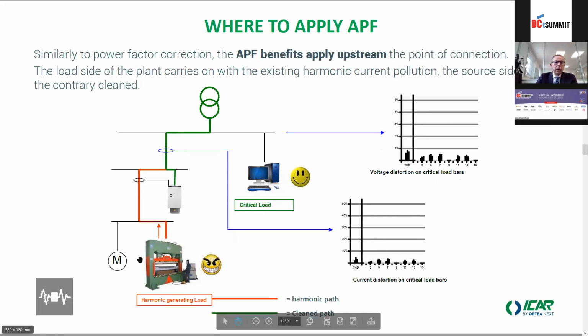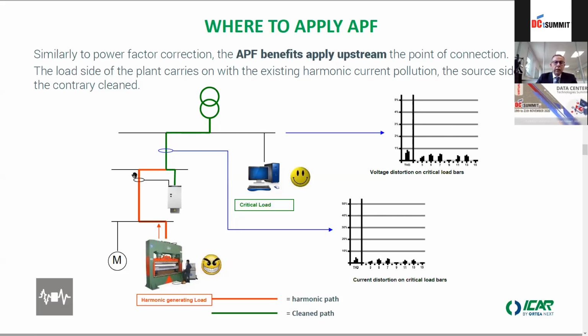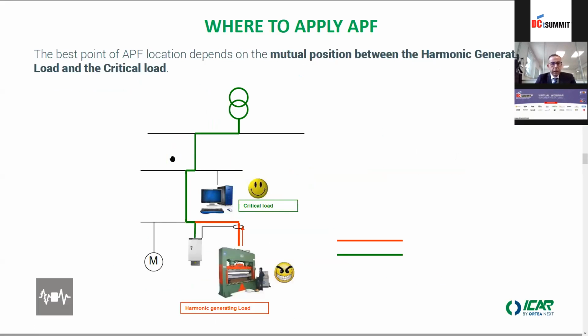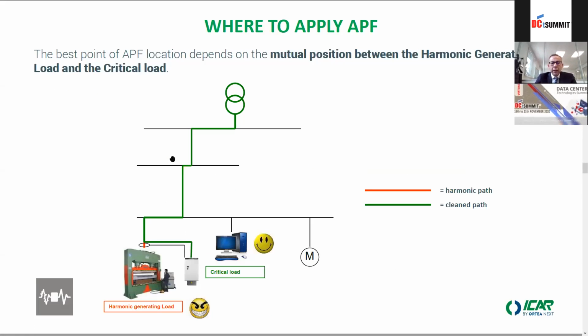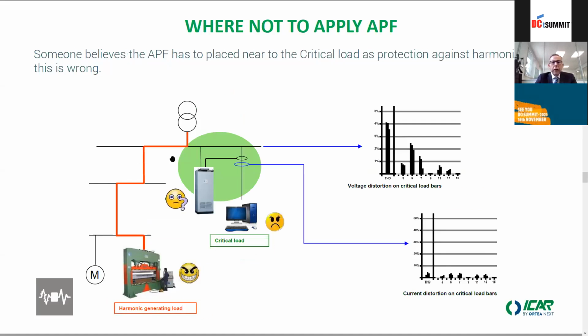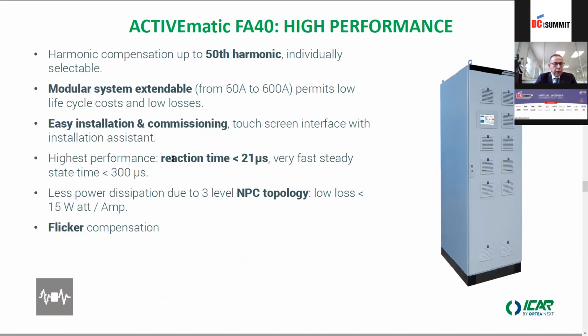So when you have harmonics circulating due to some machines, etc., you can put a harmonic filter in the right position to avoid that this can circulate all over the line, and to avoid extending the harmonics inside the line. So here you have how to apply and where to apply a harmonic filter. This can be done here locally in our factory. You can send us your measurements and data, and we can give you the SLD, and give you the right solution to help you make the better choice and better positioning of your active filter in your appliances.